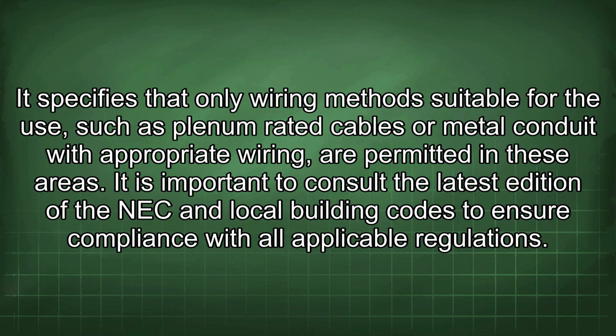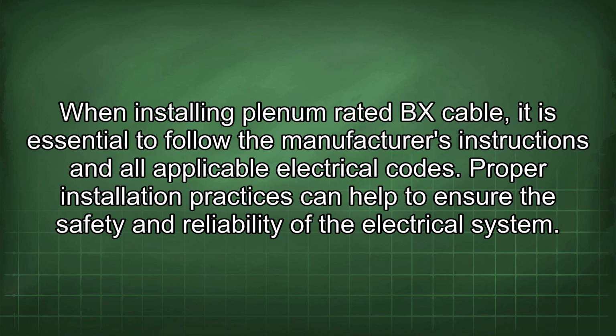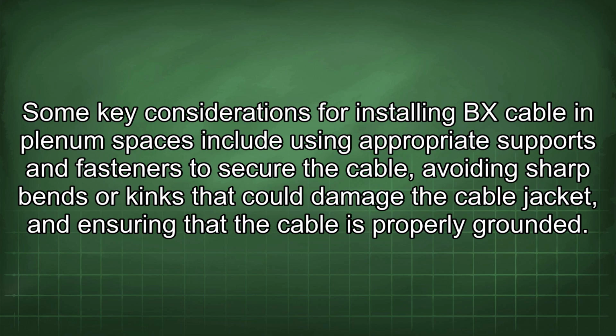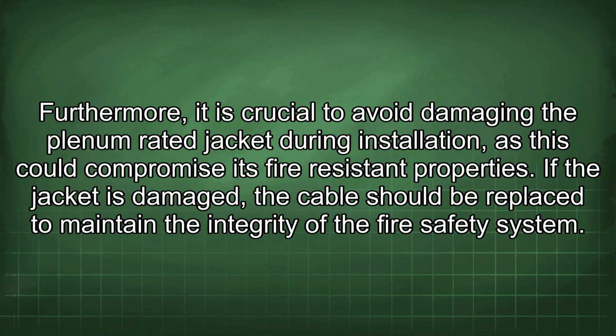applicable regulations. When installing plenum-rated BX cable, it is essential to follow the manufacturer's instructions and all applicable electrical codes. Proper installation practices can help to ensure the safety and reliability of the electrical system. Some key considerations for installing BX cable in plenum spaces include using appropriate supports and fasteners to secure the cable, avoiding sharp bends or kinks that could damage the cable jacket, and ensuring that the cable is properly grounded. Furthermore, it is crucial to avoid damaging the plenum-rated jacket during installation, as this could compromise its fire-resistant properties. If the jacket is damaged, the cable should be replaced to maintain the integrity of the fire safety system.